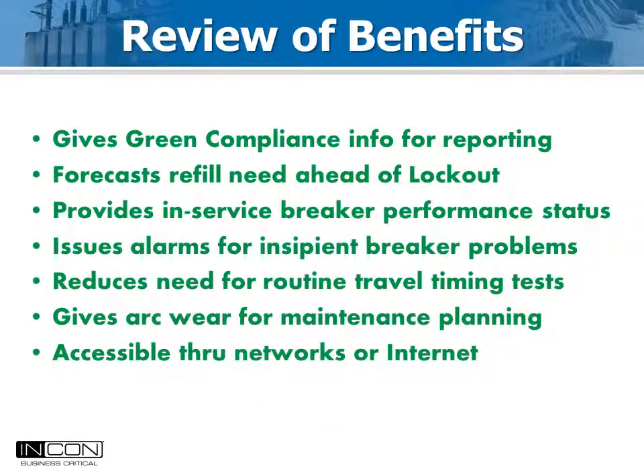The Optimizer 2 offers many benefits. It will totalize the lifetime use of SF6, making EPA reporting compliance easy. It will obviate the need for offline circuit breaker testing. First trip information will show any degradation in performance over time. And it migrates the SF6 system integrity function toward the active and predictive smart grid realm.